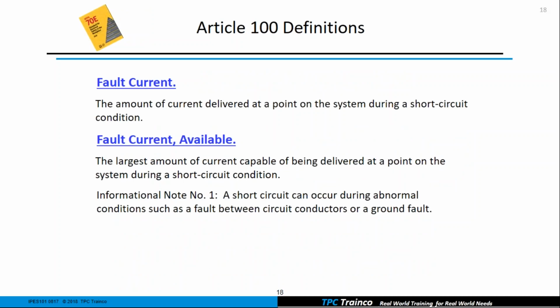They gave us some new definitions also, and they did a good job with this, I believe. A lot of the terminology in 2015 might have said short circuit current. Well, now they really want to get to fault current to include not just short circuits, but also ground faults. So available fault current: the largest amount of current capable of being delivered at a point on the system.